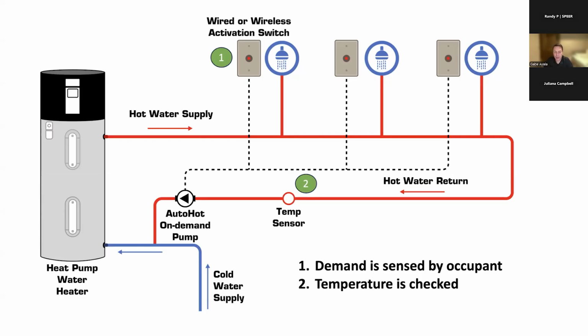And then once the temperature is checked, if it's at or above its target temperature, the pump does not turn on. It stays off. So let's say somebody just used hot water, it's in the line, somebody else goes in there and pushes a button, the pump does not turn on. And then the pump is only going to run until the temperature is satisfied. So as a result, the pump typically doesn't see more than about 10 to 15 minutes of runtime per day in total. And compare that with other control types that have the pump running for 4, 8, 12, or even 24 hours a day.